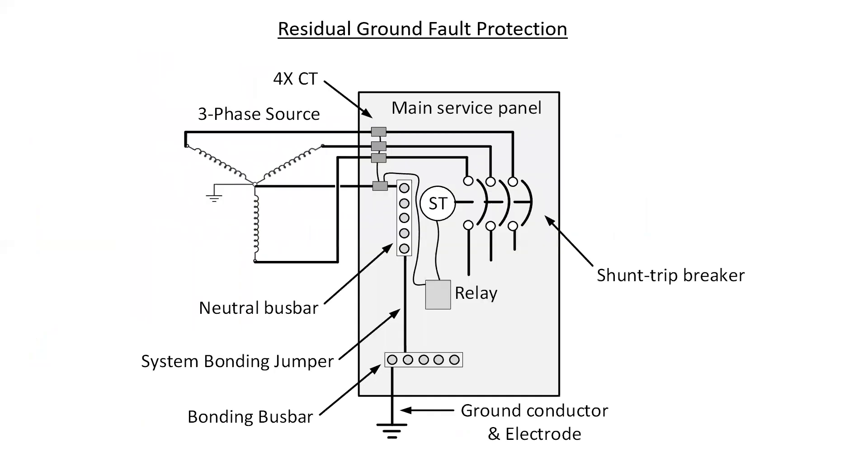The final one is residual ground fault protection. Very similar. It does exactly the same thing, but instead of having one large CT, it has four individual or smaller CTs. Now this style is often built into a ground fault protection breaker.